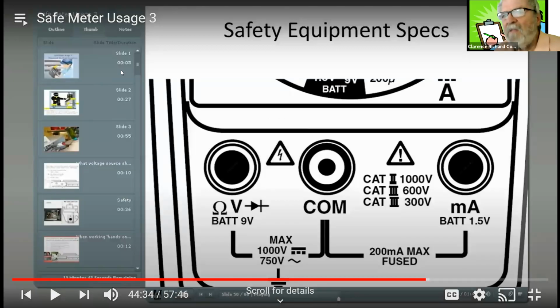Okay, so let me get into this right here. The stuff under your control panel, those are all good things to be able to report information back to. Some of that wire goes to your motor control, and in your motor control, that 110 volts gets mingled in with your 480. It's when you open up those cabinets that you start to get yourself exposed to what's going on. So if you feel safer just with the under the cabinet, that's all good information to be getting, or out there at the plant where there's limit switches and solenoid valves and things like that.